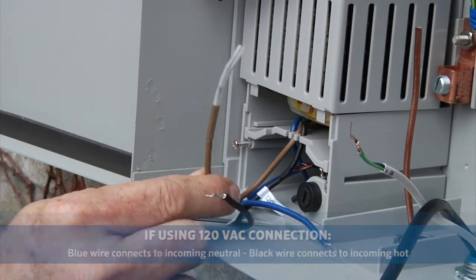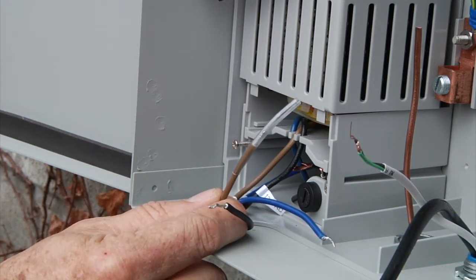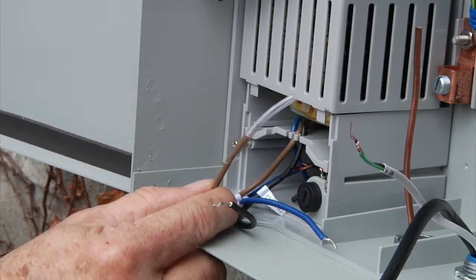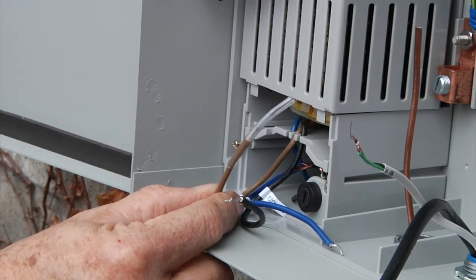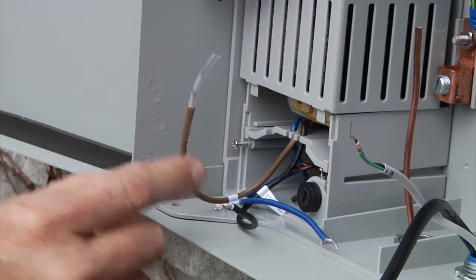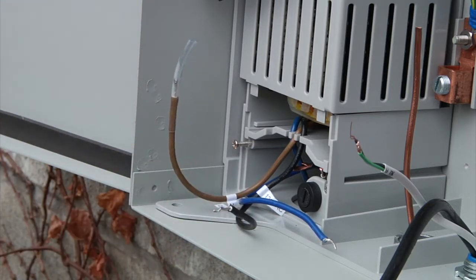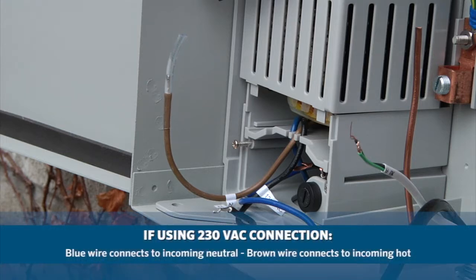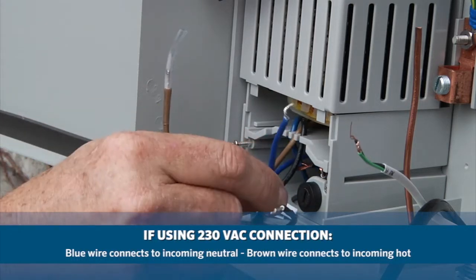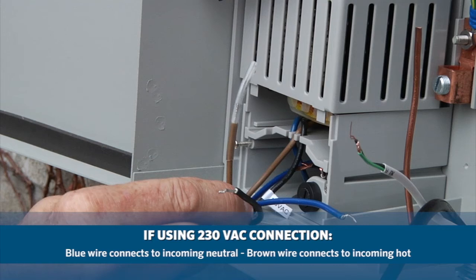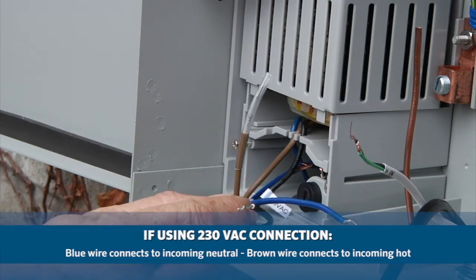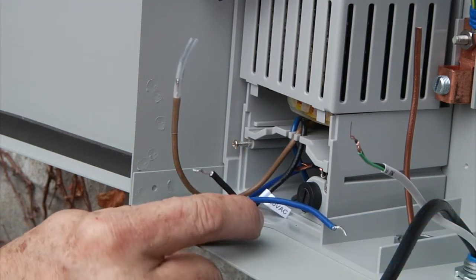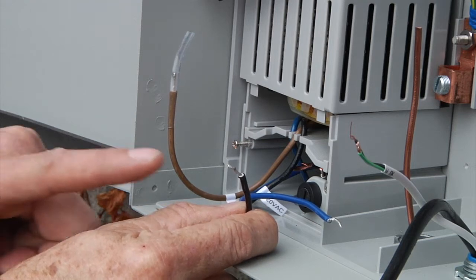That's going to leave this brown 230 wire extra, and you want to make sure that you do cap it off correctly with a wire nut and/or electrical tape, so as to protect it, because it will be hot during operation. The same holds true if you're using a 230 application. You'll use the blue wire for your neutral, and you'll use your brown wire for your incoming hot. Once again, that'll leave the black wire for 120 not used, and you will want to cap it off as well.